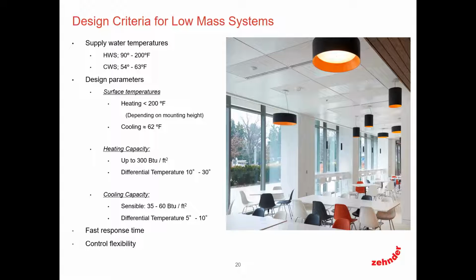Generally, you would design those a little bit higher, somewhere between 4 to 5, because they're utilizing the building mass as the condition, your active surface area, and they take a little bit longer to react. These being lightweight, fast reacting panels, they dissipate their energy very quickly. So you can design a little bit closer to your dew point and get more BTUs per square foot out of them. And thus, getting more BTUs per square foot, you could utilize less active area.